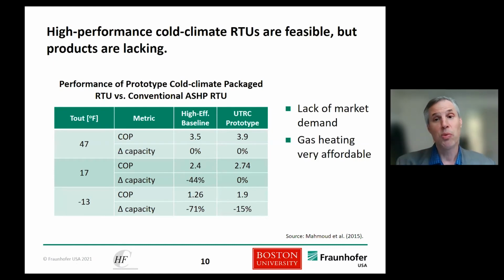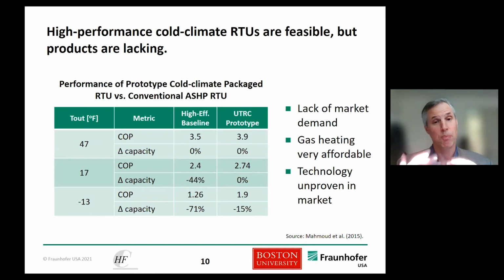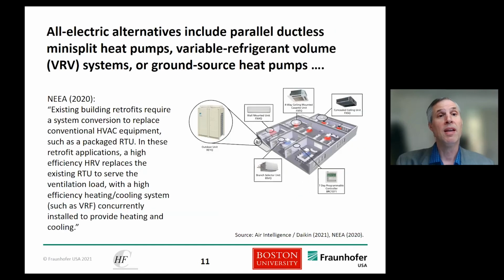Gas heating is very affordable at this point in time. Why would someone switch? And also this technology is not proven in the marketplace. The products just aren't there at this point in time. So another approach that people were talking about, and you can see the Northwest Energy Efficiency Alliance talking about it, works pretty well in new buildings. You have a dedicated outdoor air system, which brings in the outdoor air, and then you meet the other space conditioning loads through a combination of ductless mini split heat pumps and variable refrigerant volume systems. Potentially ground source is another very interesting approach, which can work in some cases.